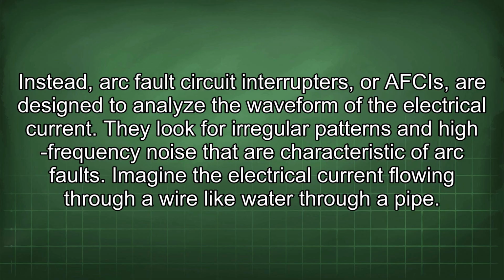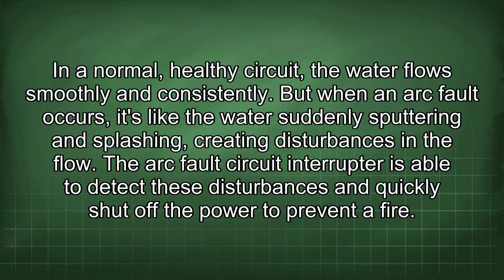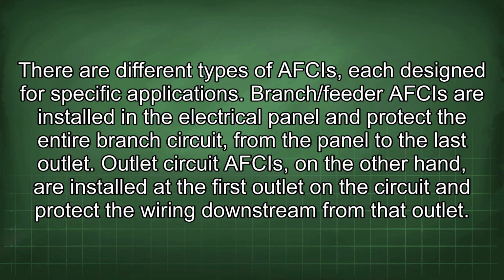Imagine the electrical current flowing through a wire like water through a pipe. In a normal, healthy circuit, the water flows smoothly and consistently. But when an arc fault occurs, it's like the water suddenly sputtering and splashing, creating disturbances in the flow. The arc fault circuit interrupter is able to detect these disturbances and quickly shut off the power to prevent a fire. There are different types of AFCIs, each designed for specific applications.